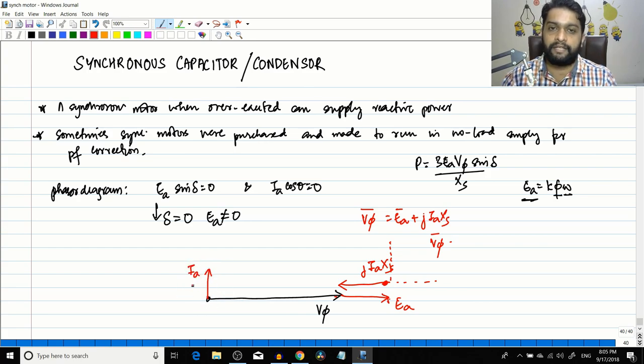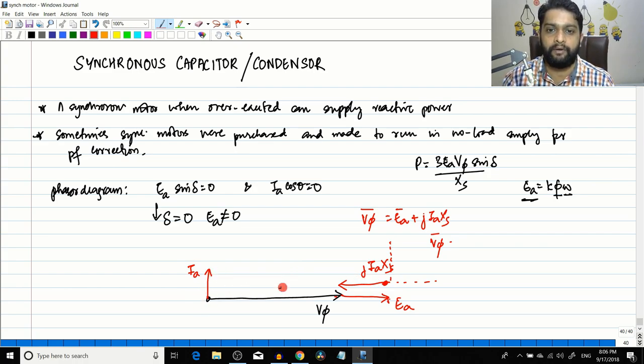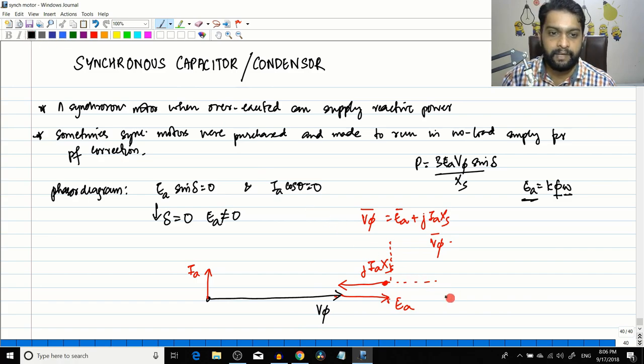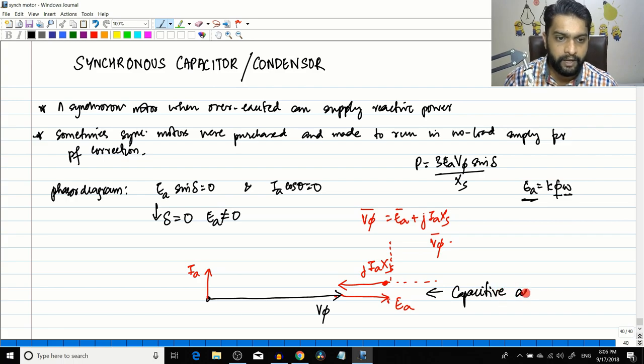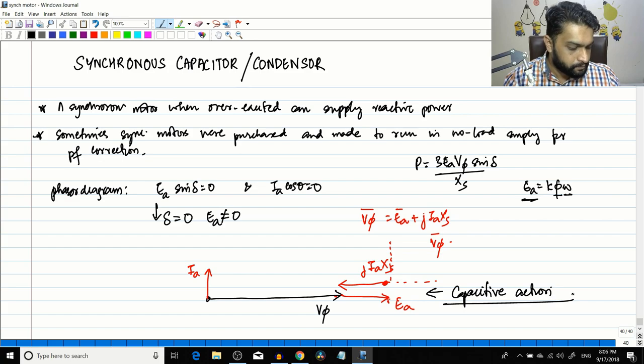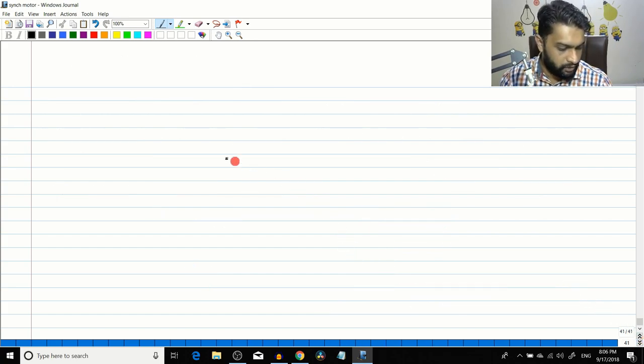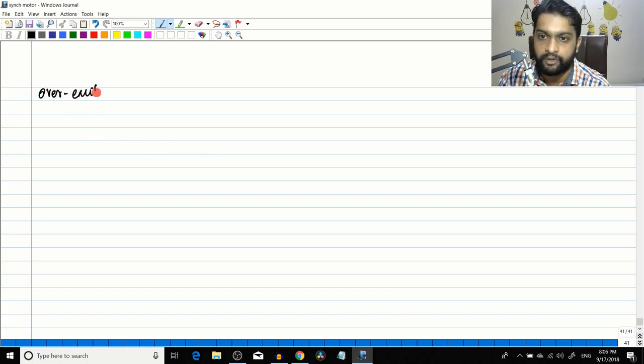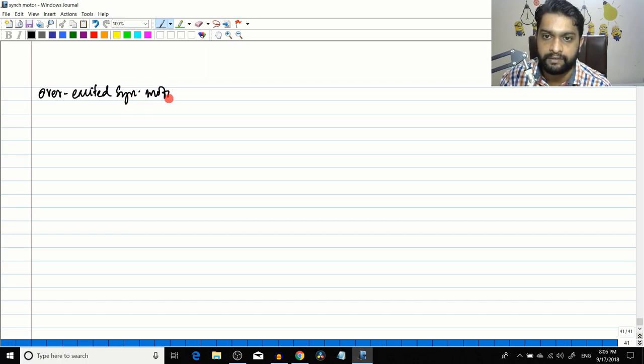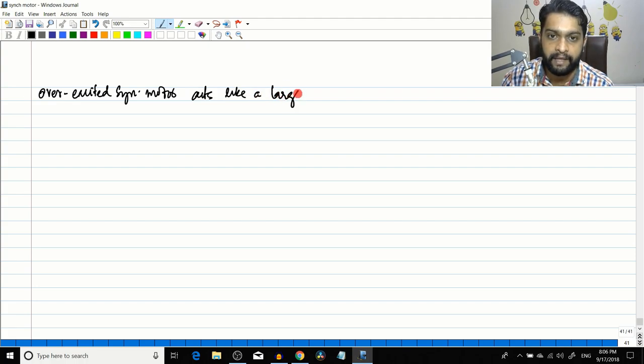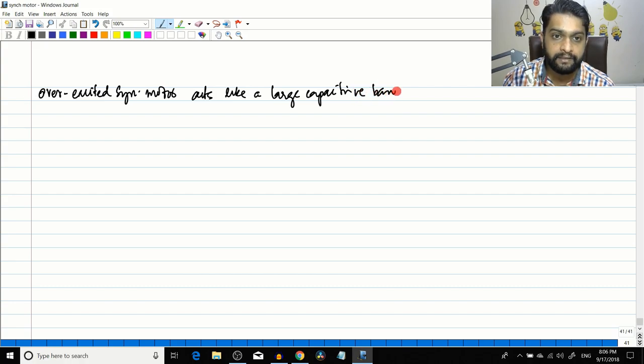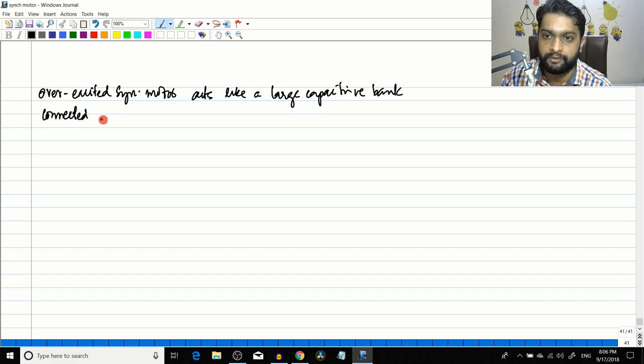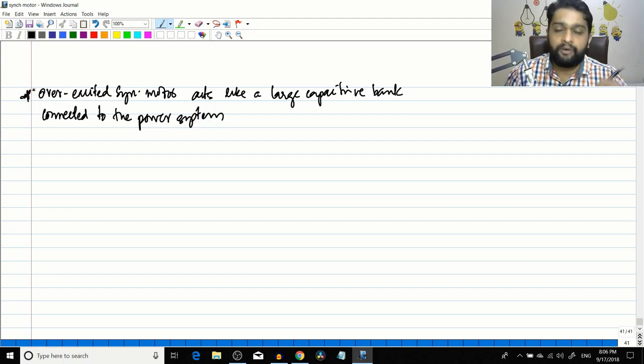If j * Ia * Xs is in this direction, naturally the current will be in the leading direction. It's a small amount of current because it's in no-load condition, so these values will be very small. You can see that here the current Ia is leading V_phase by 90 degrees. This is very similar to a capacitive action. So the synchronous motor is basically behaving like a capacitor, with the current leading the voltage by 90 degrees.